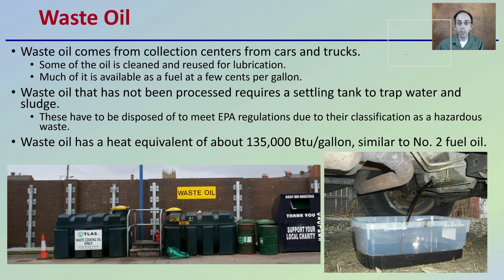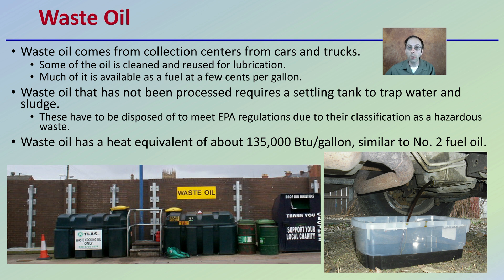Lastly, there is waste oil. Waste oil comes from collection centers from cars and trucks. Some of this oil is cleaned and reused for lubrication, but much of it is available as fuel at a few cents per gallon. Waste oil that has not been processed requires a settling tank to trap water and sludge, which must be disposed of to meet EPA regulations due to their classification as hazardous waste. Waste oil has a heat equivalent of about 135,000 BTUs per gallon, which is very similar to number two fuel oil — so it can potentially be a lot cheaper, though it does require some specialized equipment.